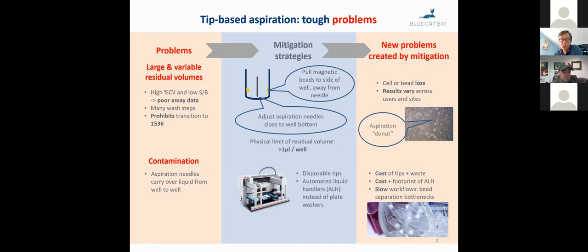So if you have a large residual volume, that means that you have a lot of background in your data. If it's variable, that means you have a lot of percentage CV. And so you will need many wash steps. And as you get into denser and denser plate formats, particularly 1536, it's really hard to do.